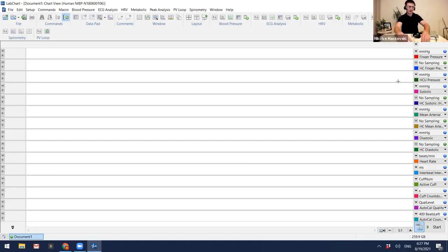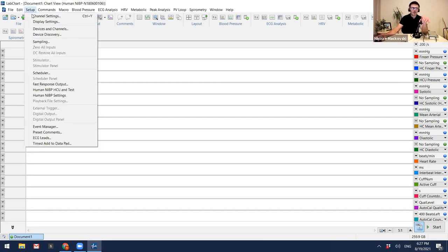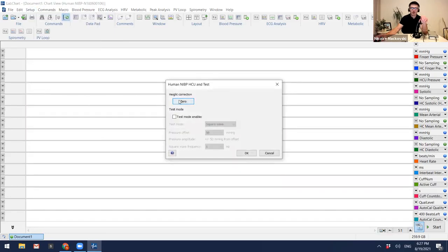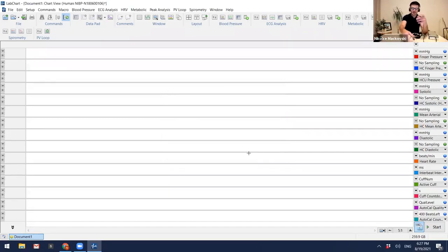So the first step here is to connect the transducer and the reference end, go to Setup, then go to Human NIBP HCU and Test. From here, we want to do height correction and zero it. This is a test mode we can use just to test the cuff itself. But to be honest, if it can actually start working, then there's no need to do any testing, so you shouldn't worry about this. As you can see here, this is correctly zeroed. Once that's done, let's put it on.